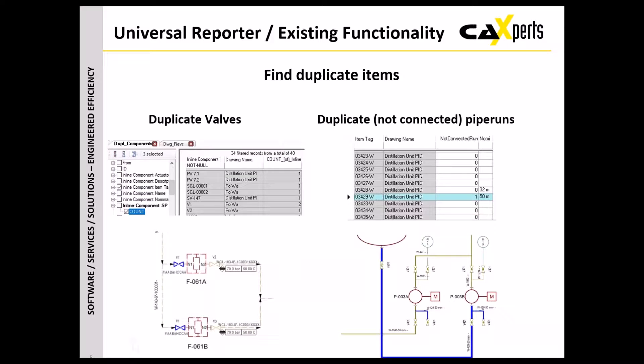In the chapter about finding duplicate items, I'm going to show two examples. The first example will allow you to find duplicate valves and eventually display them on the PID so that they can be changed and modified. Another important topic is that in the PIDs it's not so easy to identify if you have duplicate item tags which are graphically not connected. This is why we have introduced an attribute called 'not connected run'. If it displays a value different than zero, it means that this pipe run has some graphical connectivity problem.